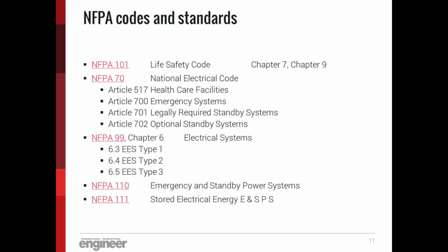Absolutely. So my question relates to your experience when we have a TIA that makes a revision to a section. For example, the 2017 edition of NEC had a 700.10d3, which referenced healthcare facilities and occupancies under the fire-rated section on emergency power. But then that was removed a year and a half later in a TIA. And the code officials might actually be looking at a book that has the old version. How do you see that adoption take place when there's a TIA that makes a change like that?